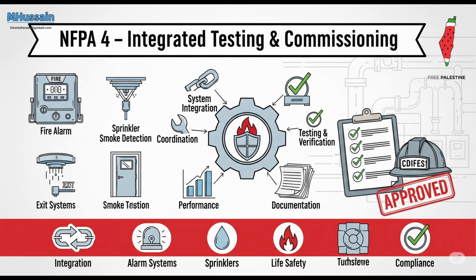And these scenarios must include specific events, like simulating a loss of normal power to see what happens. What else? Simulating water flow from a sprinkler system, or the presence of smoke-activating detectors. Now, for periodic testing later on, you are allowed to use simulated events to trigger the initiating devices. So you don't actually have to, like, start a small fire or flood the place every year? Thankfully, no. Simulated inputs are fine for routine checks, but the system has to react as if it were real.